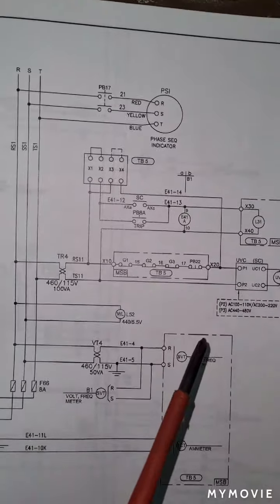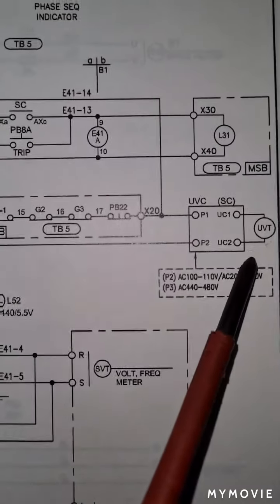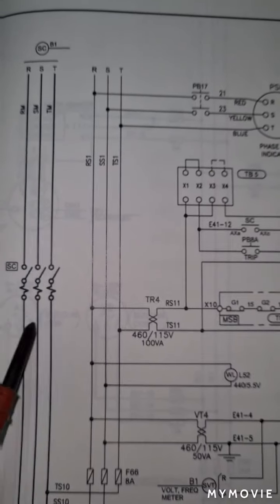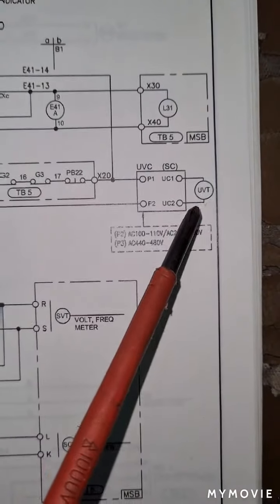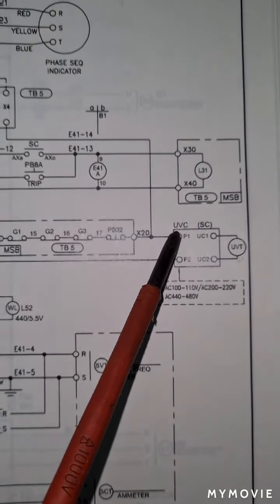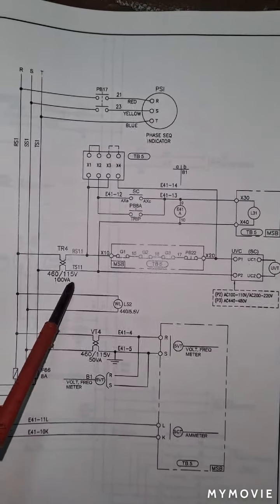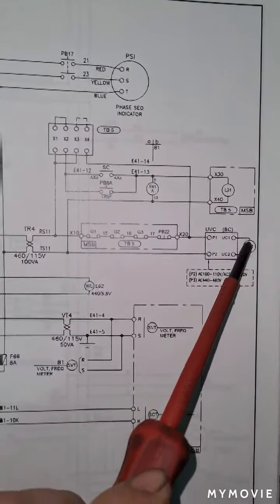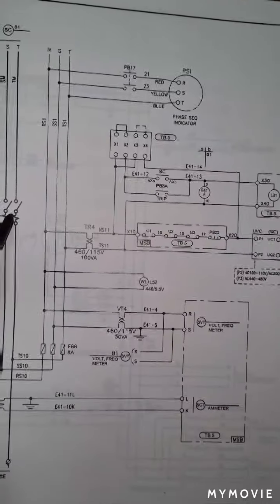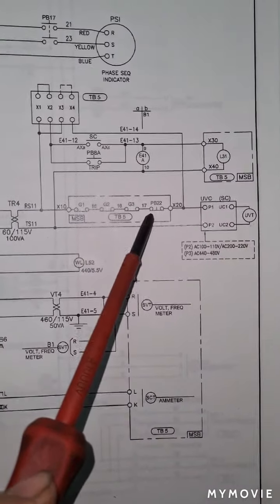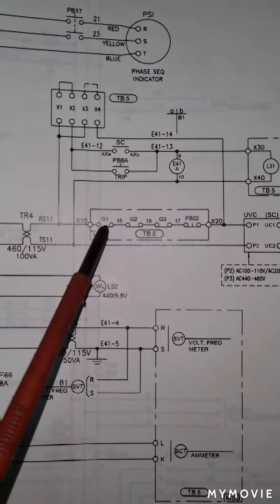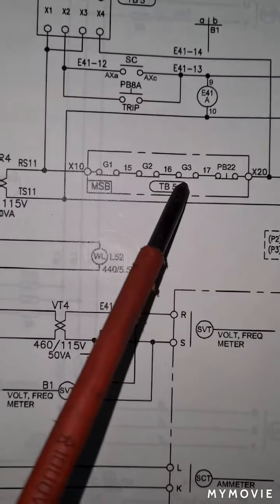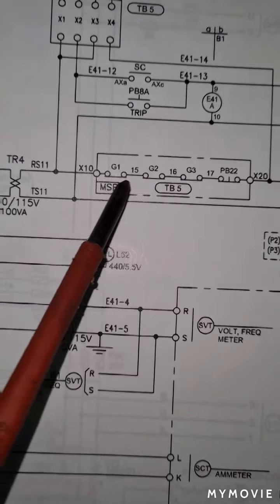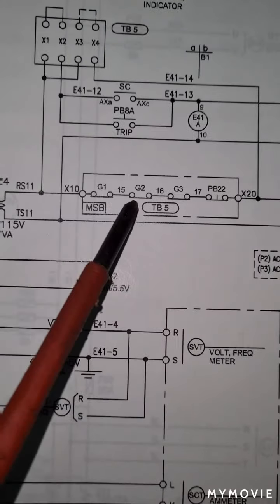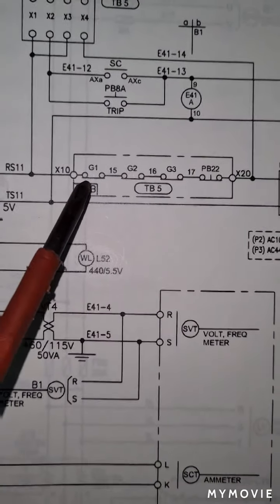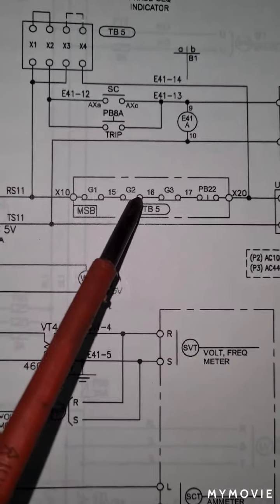Then, in order for you to switch on the shore connection circuit breaker, you must energize the undervoltage coil. In order to supply 115 volts to the UVT coil of the air circuit breaker of the shore connection breaker, generator 1 circuit breaker, generator 2 circuit breaker, and generator 3 circuit breaker must all be off. Once the generator 1, 2, and 3 air circuit breakers are switched off, there are auxiliary contacts, normally closed contacts.